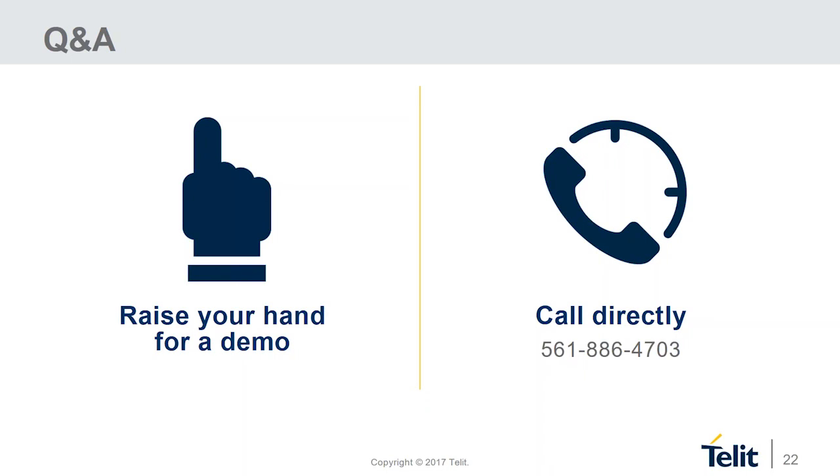With DeviceWise, we've created a product called an Atom 16, with Telit. It's a digital and analog to Ethernet conversion, if you will. It's pretty low cost for all the functionality you get, and it will take digital signals from CNCs and old equipment. We can parallel off of stack lights for the green, for in cycles, and analog values, and it sends it to DeviceWise, and then on the DeviceWise side, you can do some simple calculations for efficiencies. You can monitor downtimes and uptimes. We have hundreds and hundreds of them in the field.